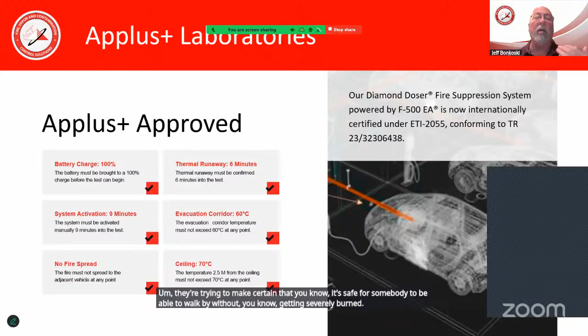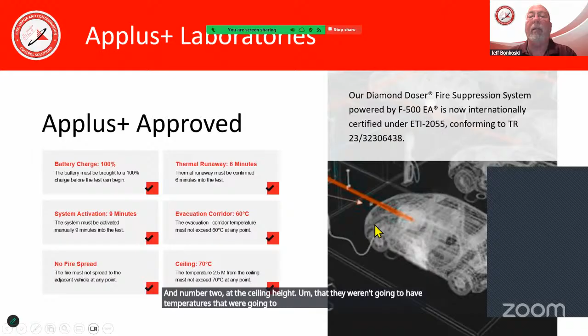In the evacuation corridor I mentioned, the temperature could not exceed 60 degrees C, and at ceiling height it couldn't exceed 70 degrees C. They're trying to make certain it's safe for someone to walk by without getting severely burned, and that at ceiling height temperatures wouldn't compromise the structure and cause a building collapse.